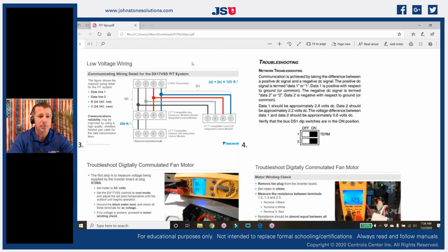So let's move down here real quick. We know that our control board is dictating the RPMs and the RPSs of the outdoor unit. So if we look at how those are going to be wired, if we take a full wiring diagram for our entire system, we are going to be at our indoor unit. So this particular one, we're actually using the Honeywell CTK04 thermostat. So we're going to have C at our thermostat and R at our thermostat, because that's just going to feed that nice big digital screen. We're going to have all of that power starting at our furnace or air handler, right? That's where our main transformer is at. So it's going to feed 24 volts to feed our nice big screen, and we're going to feed that 24 volt signal over to our cased coil or air handler, whichever one we're using. And we don't need it to the outdoor unit, because remember, with our inverter outdoor units, we already have a power source on that board. The boards stay energized 24/7 on these inverter outdoor units. So we don't need an R and C to feed the outdoor unit. We just simply need to have our communication. So when it comes to communicating, we're going to use an entire mesh network.